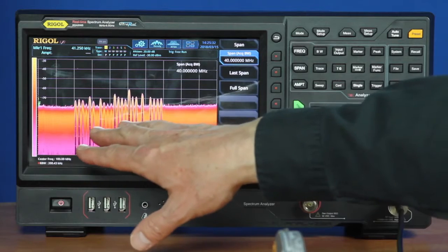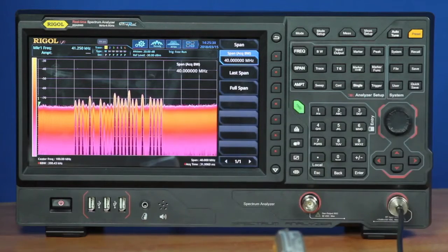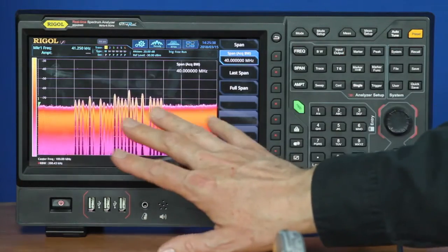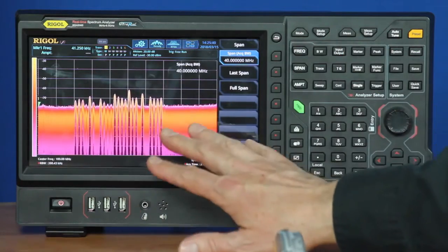Now, the trouble is that power cords and a lot of interconnecting cables are wonderful antennas at this frequency range. And when we're troubleshooting, we'll often find that the noise from the local FM stations is being picked up on these cables, and it's being observed on an analyzer. I bring that up because people will often chase these things and try to solve problems that aren't real.